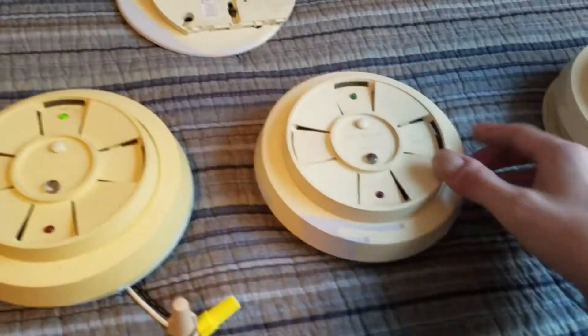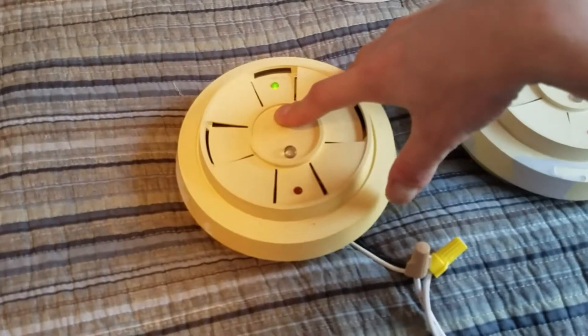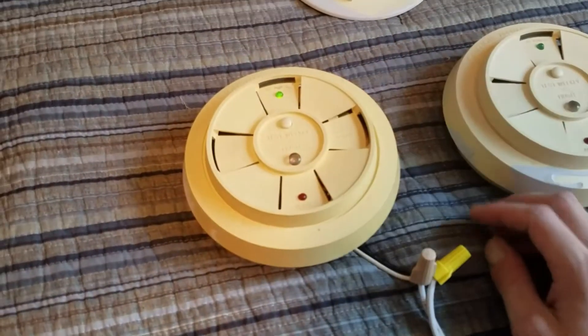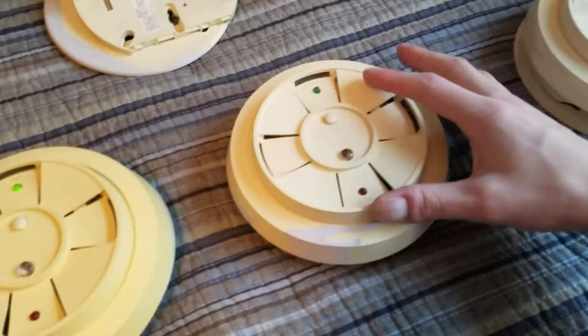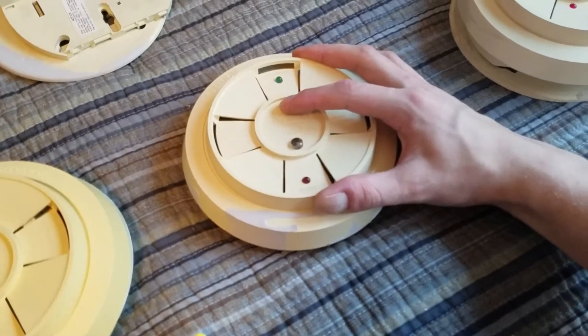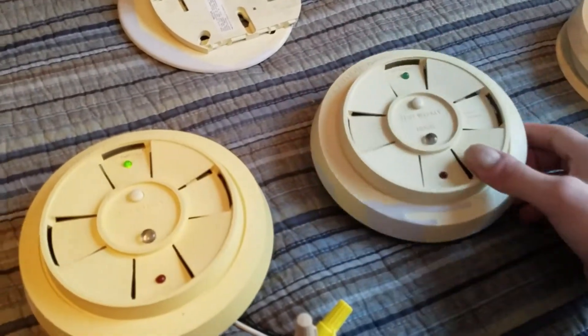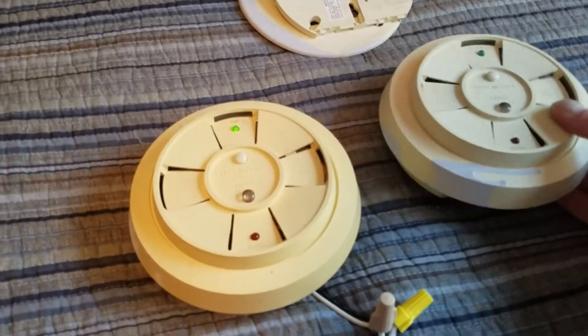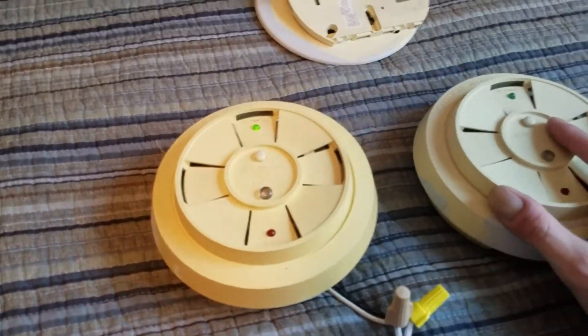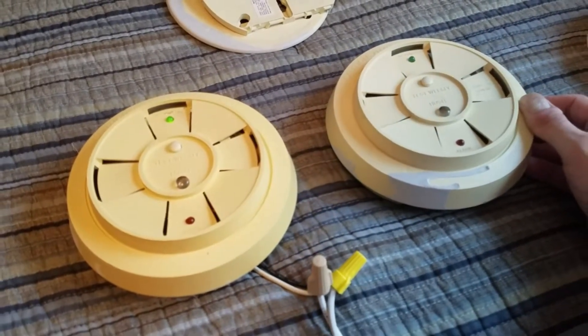So let's go ahead and test them. I'm going to start with the one that's powered on AC power, and then we'll go to the one that's being powered on battery. That one is a little bit higher pitched, as you can hear. They both sound in a T3 pattern, which is exactly the same pattern that all the second-gen F900Ds I've heard do.